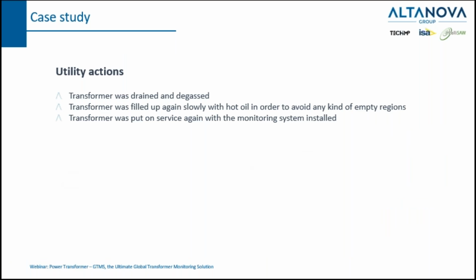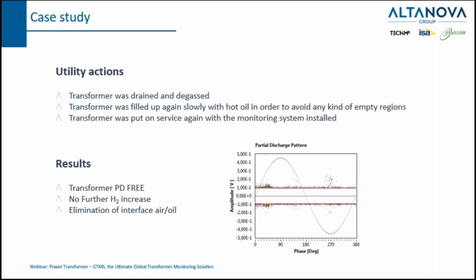Just to close this experience, the utility decided to drain and degas the transformer, and then it was filled up again, in this case with some dedicated procedure with hot oil and in a very precise manner, let me say. And the transformer was, after these activities, put in service again, with the monitoring system installed. These are the results after the actions performed by the utility.